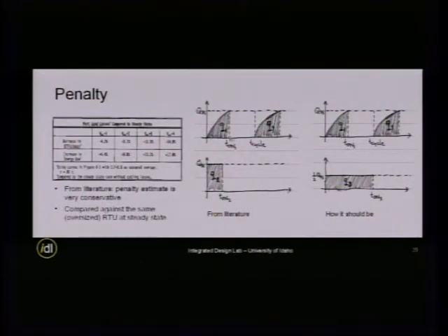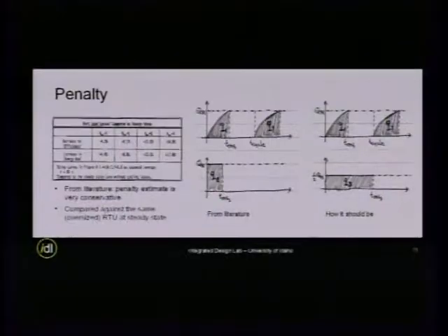This is the cycling units, on and off, on and off, right? And then what this clause means is that the penalty is calculated by the same unit, the same oversized unit, that is run steady state. So the 17% penalty will be Q2 divided by Q1. That's 17%.